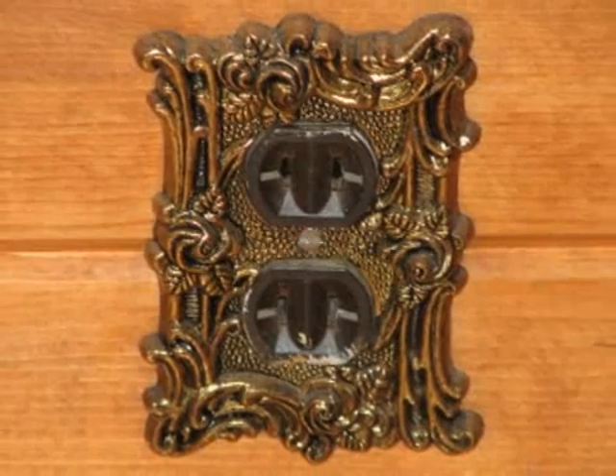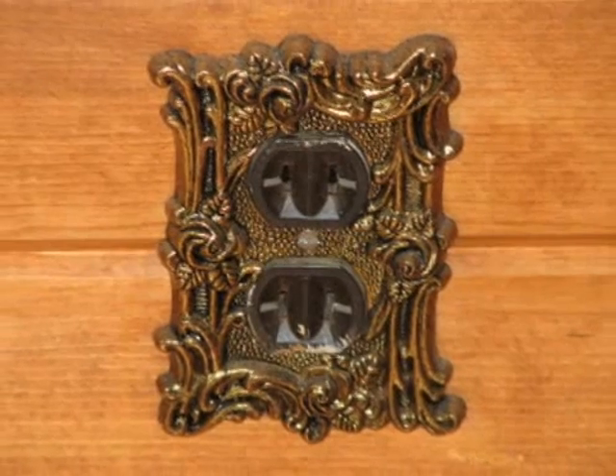Okay, I want to talk to you about two-prong and three-prong electrical receptacles, and I want to explain the difference between the two. If you didn't know it, a two-prong receptacle may actually be a grounded receptacle. The third prong has nothing to do with the grounding of the receptacle. The grounding to the receptacle comes from the system. So when evaluating two-prong versus three-prong receptacles, it's important to look at the condition of the electrical system itself.